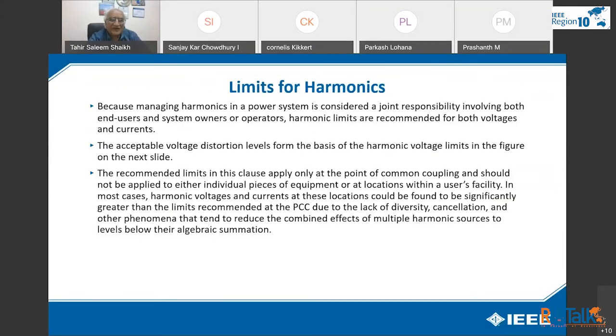Because managing harmonics in a power system is considered a joint responsibility involving end users and system owners, harmonic limits are recommended for both voltage and currents. The acceptable voltage distortion level, which forms the basis of the harmonic voltage limit, is in the figure on the next slide. The recommended limits in this clause apply only to the point of common coupling and should not be applied to either individual pieces of equipment or at a location within a user's facility. In most cases, harmonic voltages and currents at these locations could be found to be significantly greater than the limits recommended at the PCC, due to the lack of diversity, cancellation, and other phenomena that tend to reduce the combined effects of multiple harmonic sources to levels below their algebraic summation.